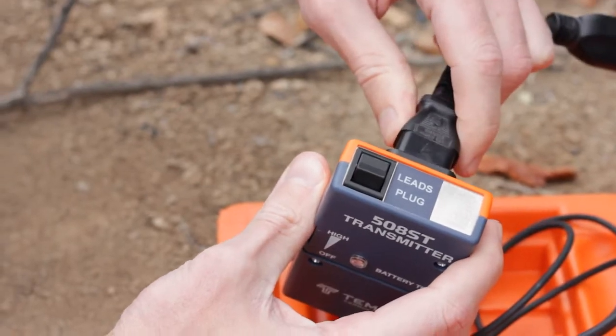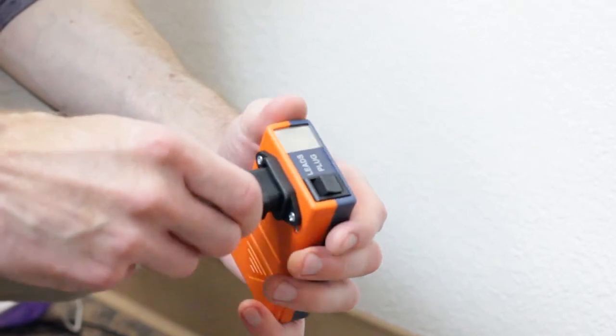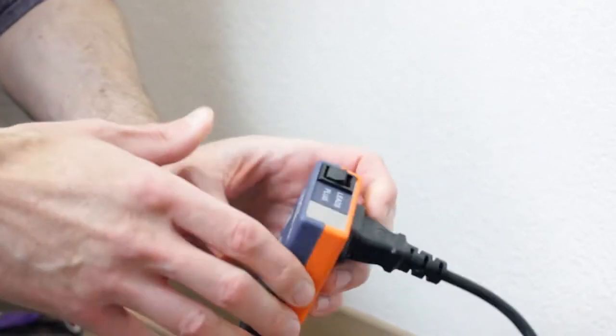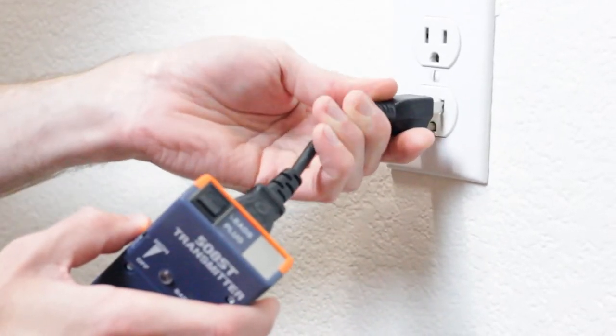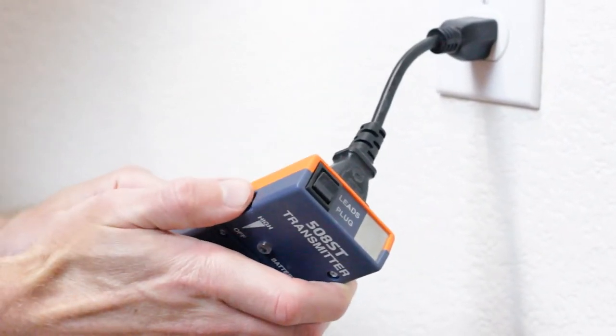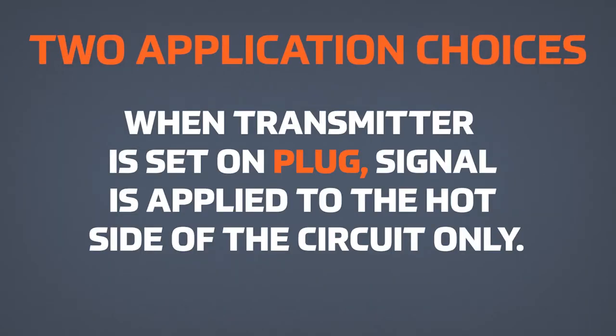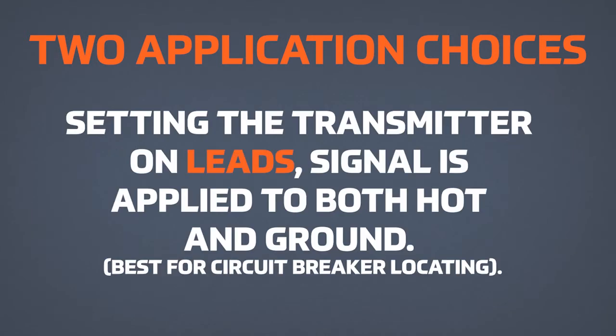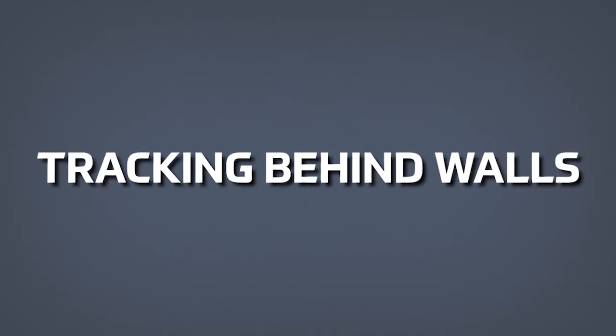When using the AC adapter plug, plug one end into the IEC socket on the back of the transmitter 508ST, then plug the AC power adapter plug into the outlet. Using the AC adapter plug, there are two application choices. When the transmitter is set on plug, signal is applied to the hot side of the circuit only. By setting the transmitter on leads, signal is applied to both hot and ground, best for circuit breaker locating.